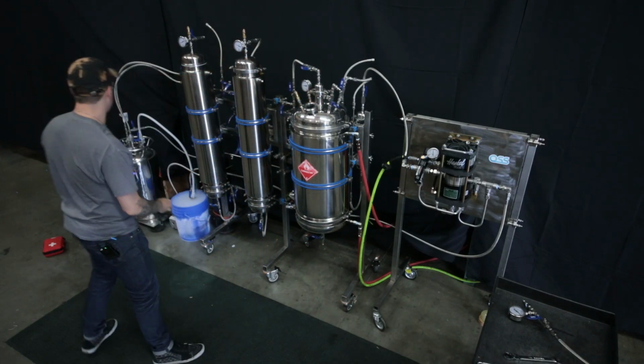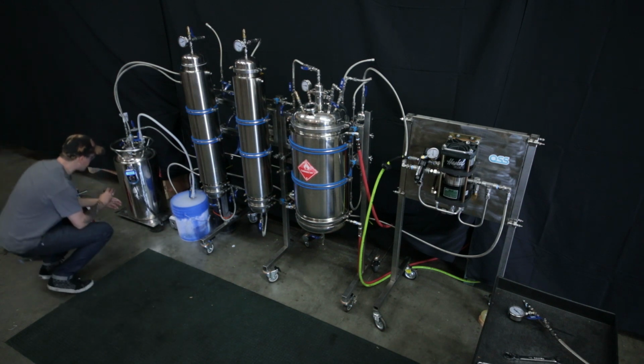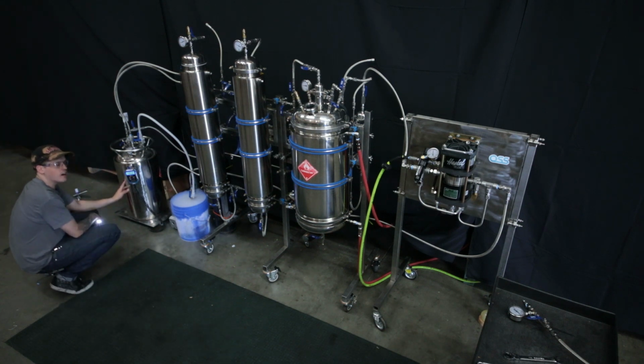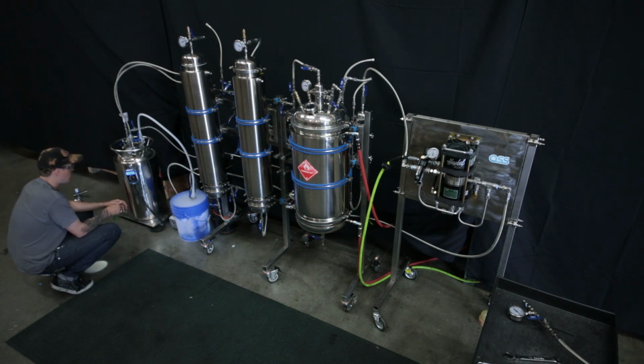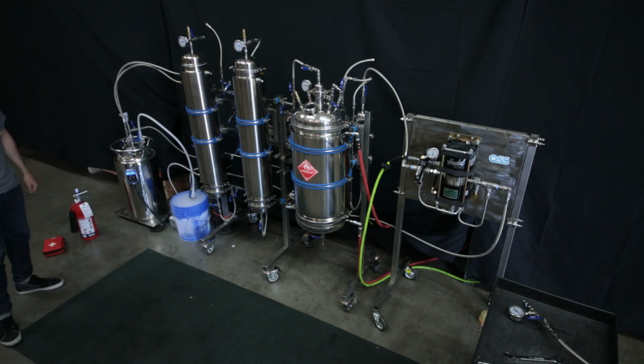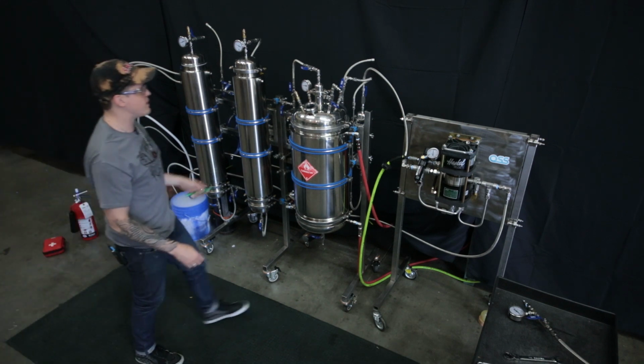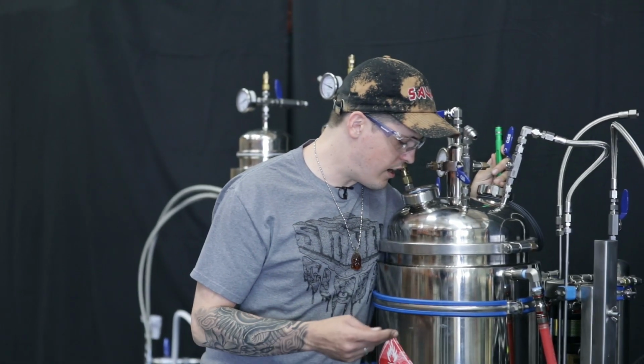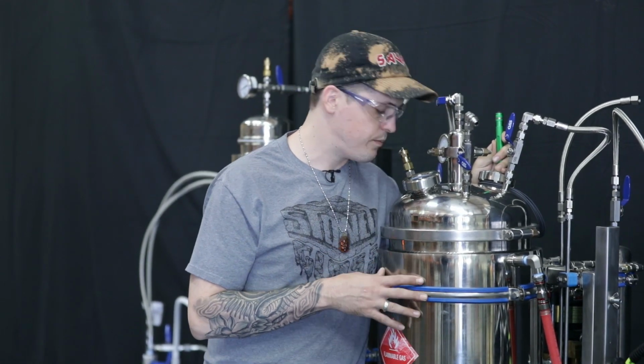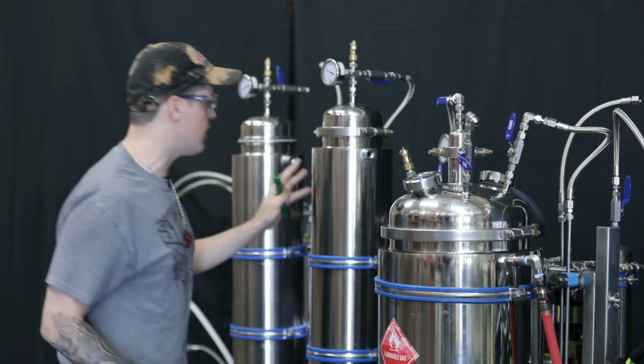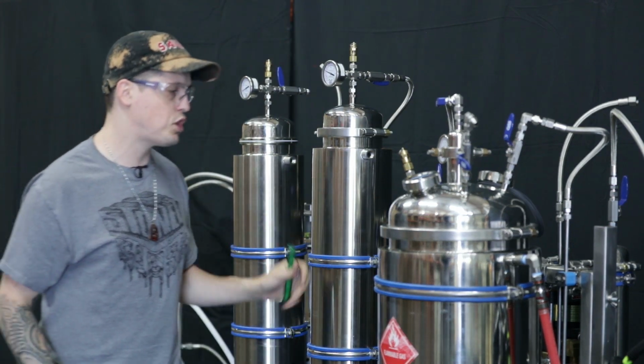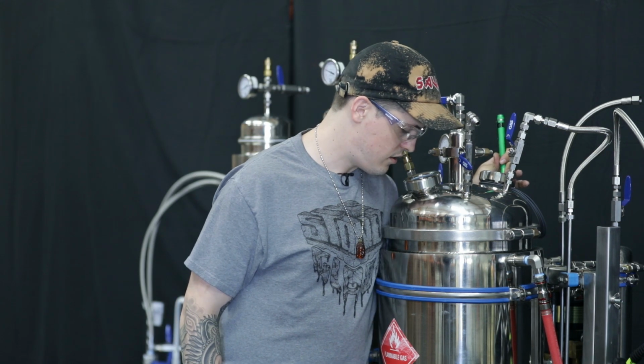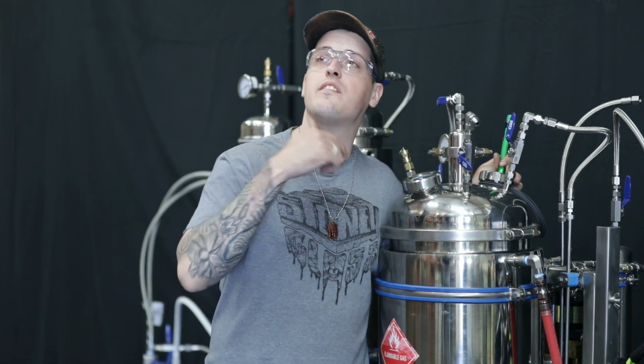Now if I go back to my tank, I should be looking at this for how much butane we've recovered. Since we started with 10 pounds, I'm looking at here for the final amount that we have remaining. So as it's recovering, we're going back towards zero. So we're at about 6.5 pounds of butane left. And so that tells me that there's butane here in this vessel, which I do still see. And there's also maybe some butane still left in our material column, which I am sure of, because I still see it flooding in right now.